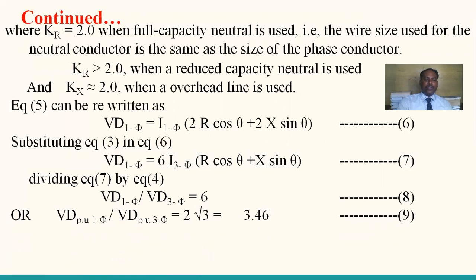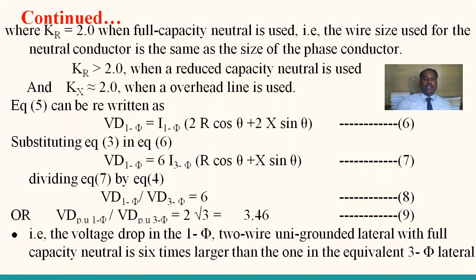And the per unit voltage drops are to be taken into account. The voltage drop of a single phase system on a per unit basis divided by the voltage drop of a 3-phase system on a per unit basis is equal to 2 root 3, which is 3.46. So the voltage drop in the single phase 2-wire uni-grounded lateral with full capacity neutral is 6 times larger than the one in the equivalent 3-phase lateral. So it is 6 times, it is too much.